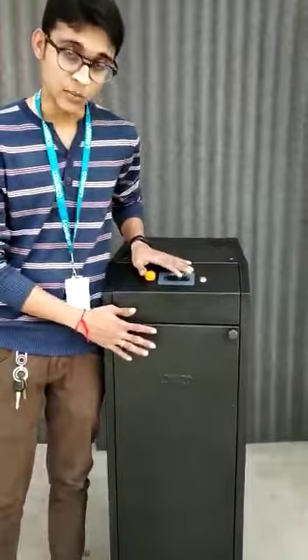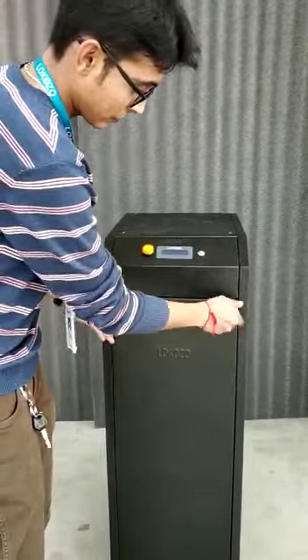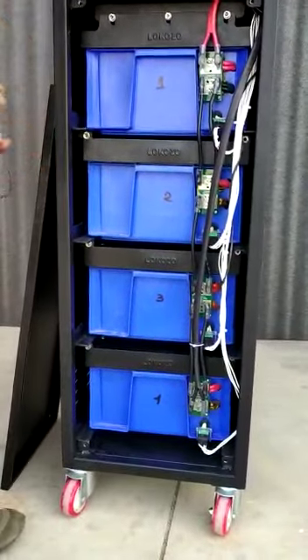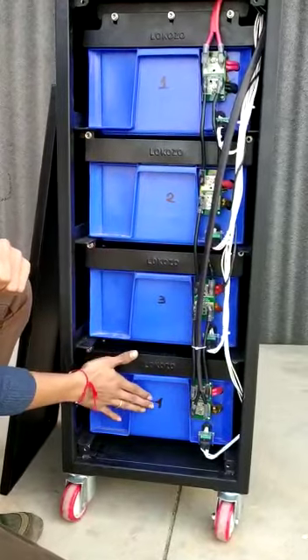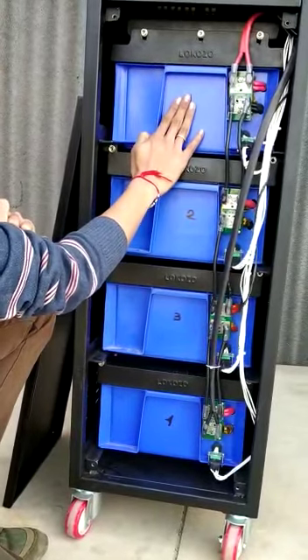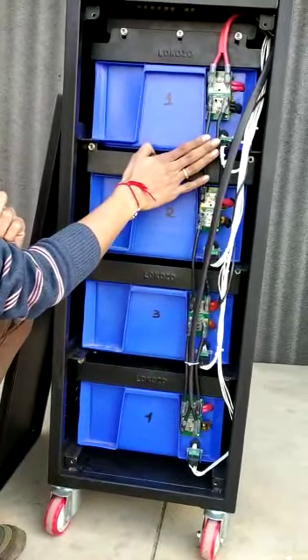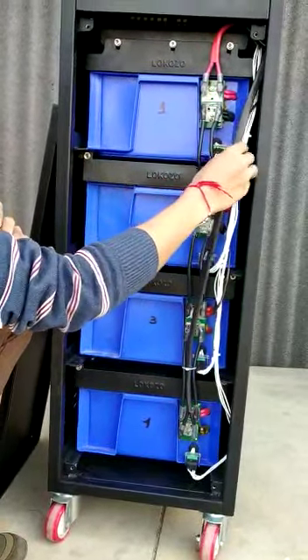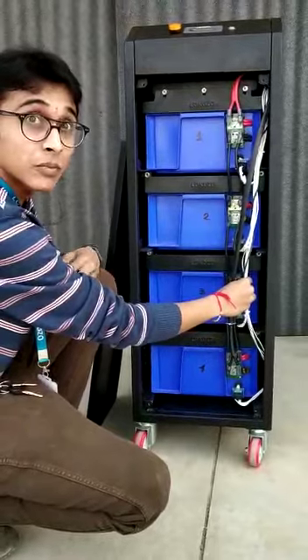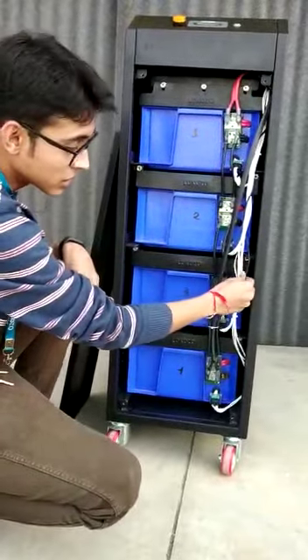Let's go through the architecture of the system. I am opening the front portion. As you can see, there are four battery racks. Each of the three lower battery racks is 12.8 volts, 210Ah capacity, and the top rack is 12.8 volts and 210Ah capacity. All four battery racks are connected in series, so the total voltage of the system will be 48 volts and 210Ah capacity. There are white cables coming out of each rack which go to the BMS for cell voltage sensing. There is also a temperature sensor connected in each battery rack.